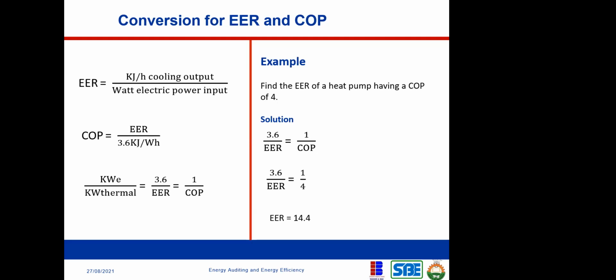Find the EER of a heat pump having a COP of 4. Now you are given a heat pump. You know the COP to be 4. And now somebody is asking, I want to know what the value of this COP is in EER. Okay, so simple solution. Remember the formula I told you to take note of: 3.6 over EER is equal to 1 over COP. You put in what you know. You know what the COP is, which is 4. So the only thing you're looking for is the EER, and you just cross multiply. By cross multiplying, you get your EER, which is 14.4. It's as straightforward as that. Okay. What if you're given the EER and you are asked to calculate the COP? It's the same thing you're going to do. Just apply the formula and you can do that conversion.